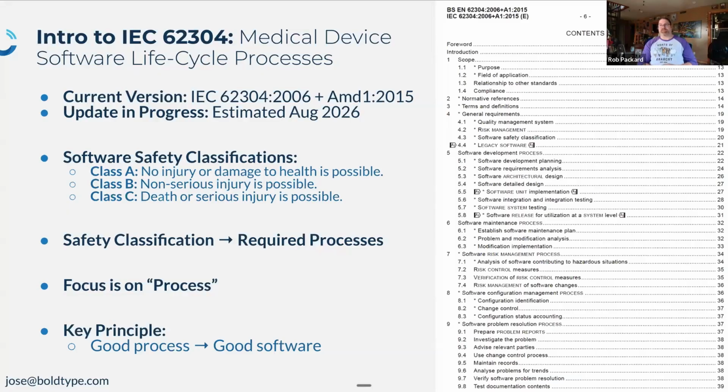I think companies, a lot of times, by not doing a really good job of architecture and risk controls, make the FDA really nervous and push themselves into enhanced sometimes. That's a good thing to keep in mind. If you're in doubt, if it's on the edge, you're probably better off treating it as enhanced. We'll talk about what those differences are. It's not the end of the world, but you're definitely going to be more rigorous and comprehensive.